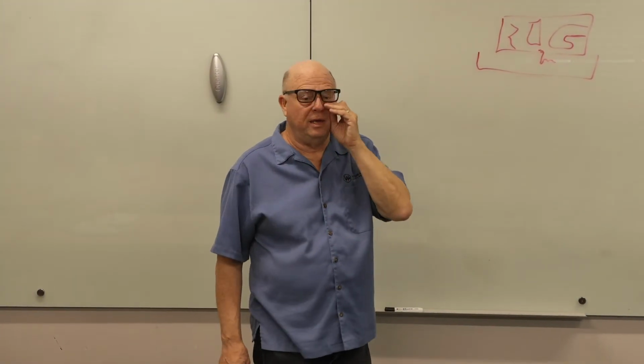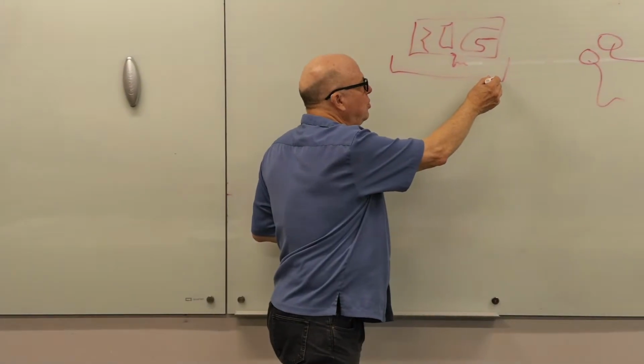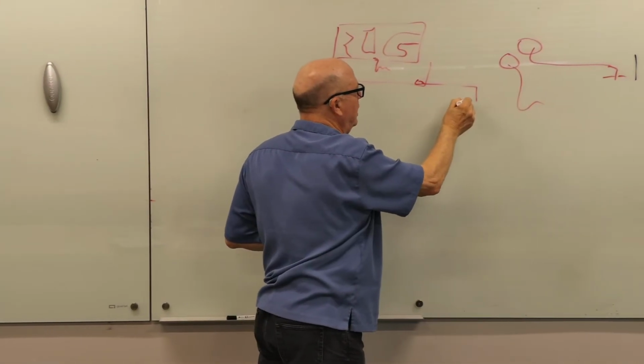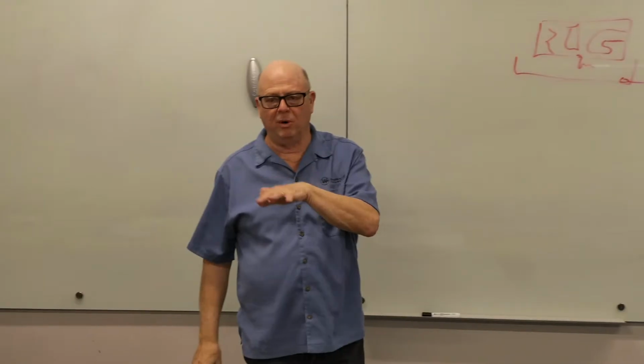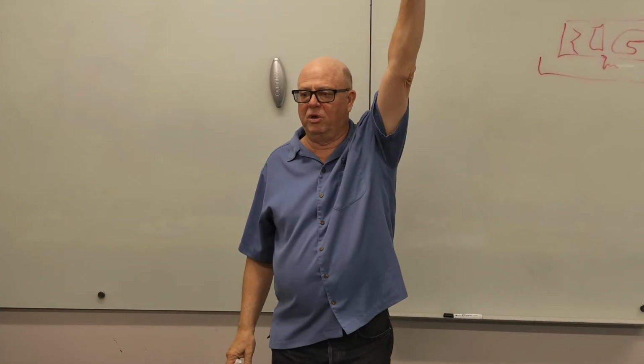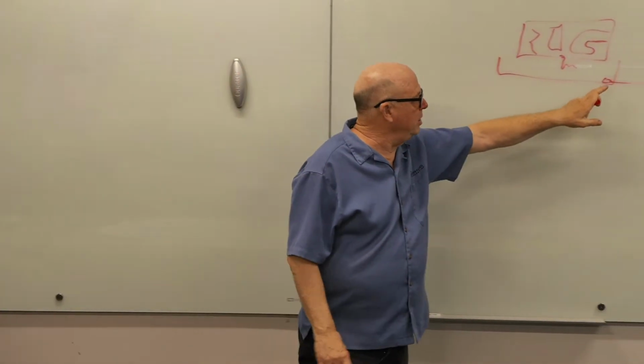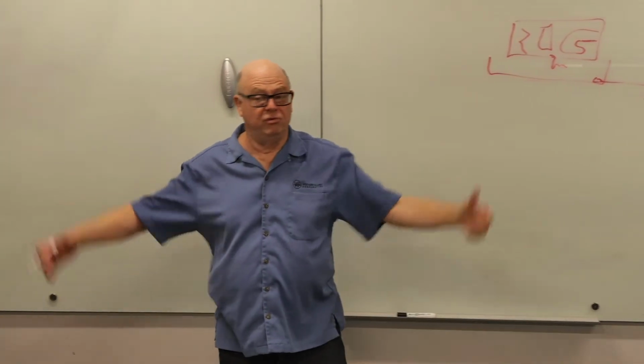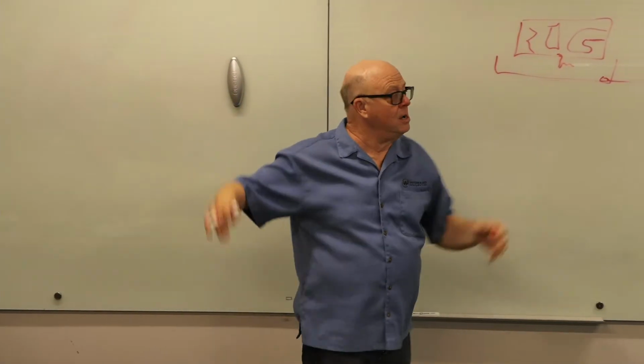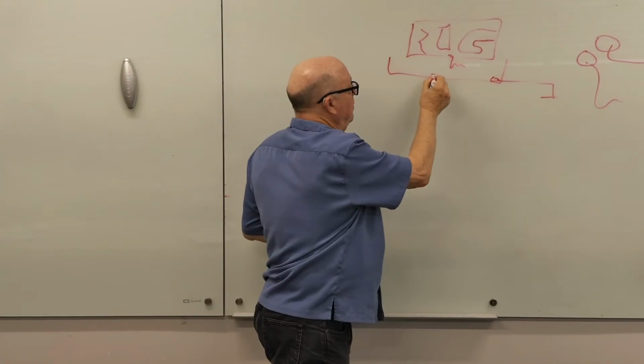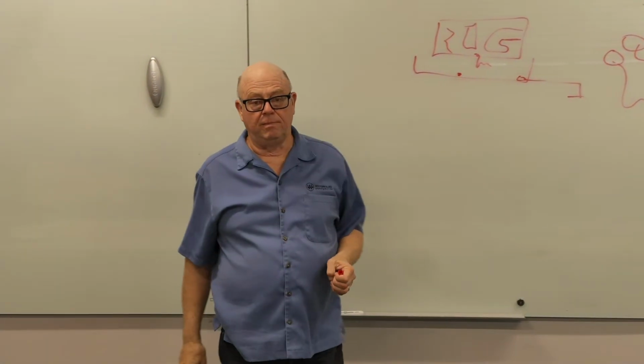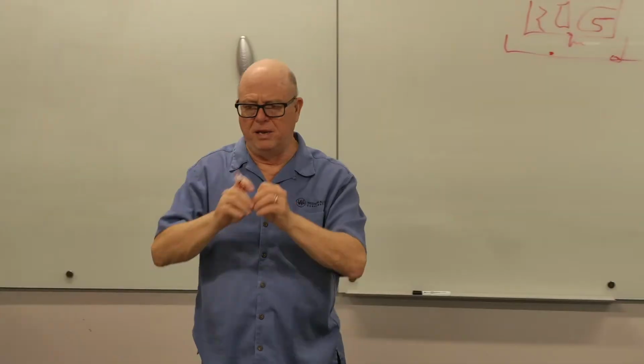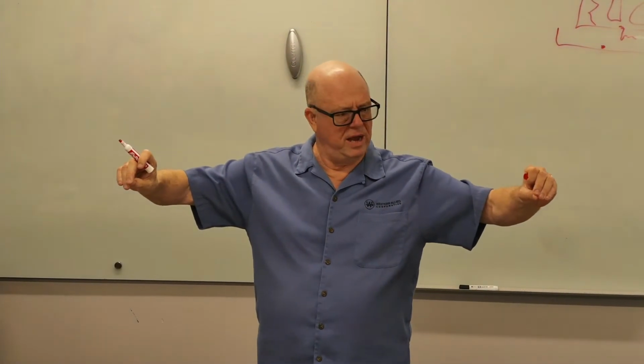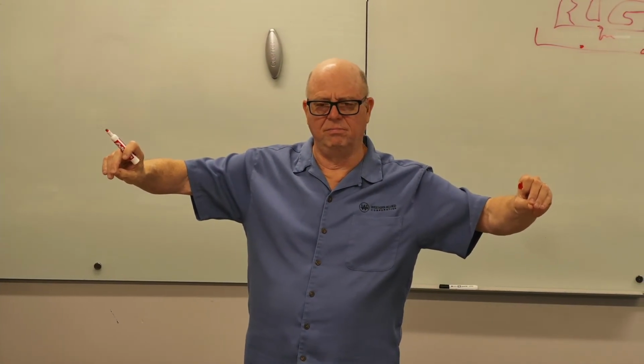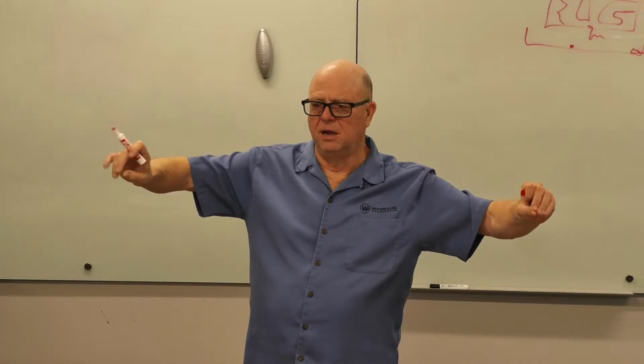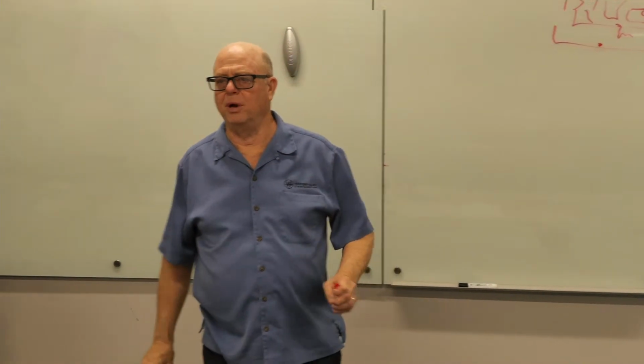And the other way is, and by the way, you could pipe this pan out to a visible location, but my memory is, and I have already told you, I am not the code maven, but my memory is it's not required. If you just got a pan, you're legit. But let's say you got a pan and then you put moisture detection in there. And we talked, I think, before about using the button versus using the cable. Did we have that conversation, or am I making it up in my brain? I'm seeing blank looks, so I'm making it up in my brain.